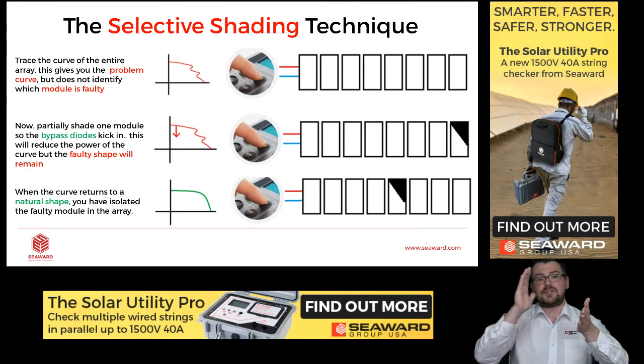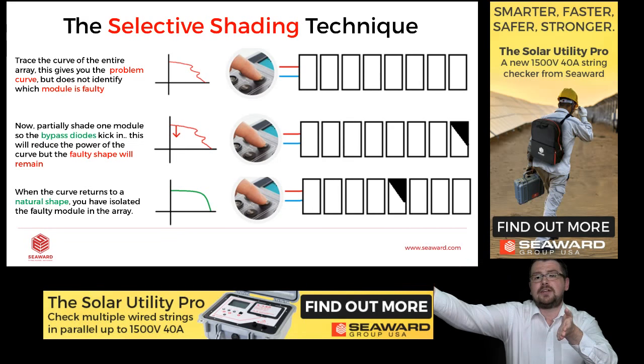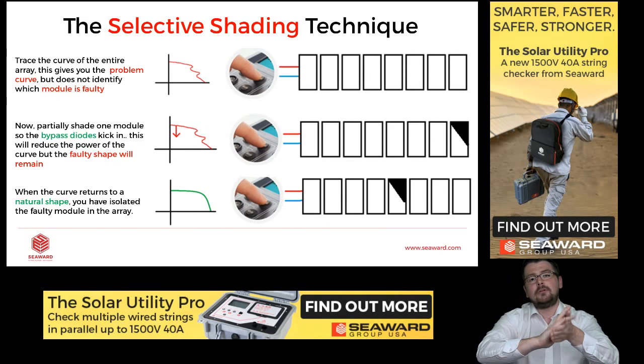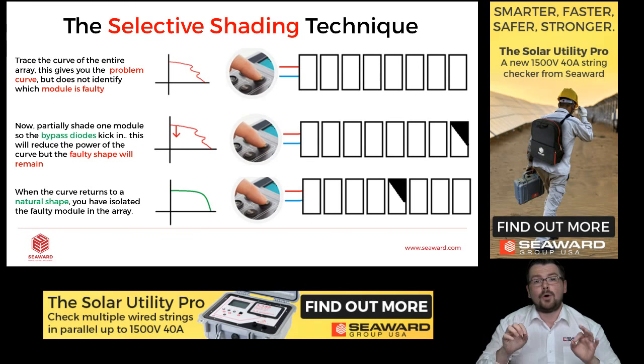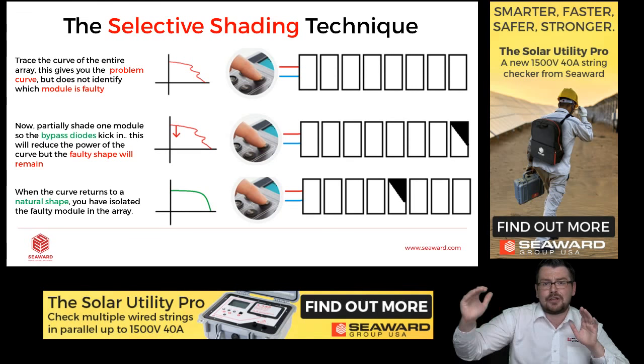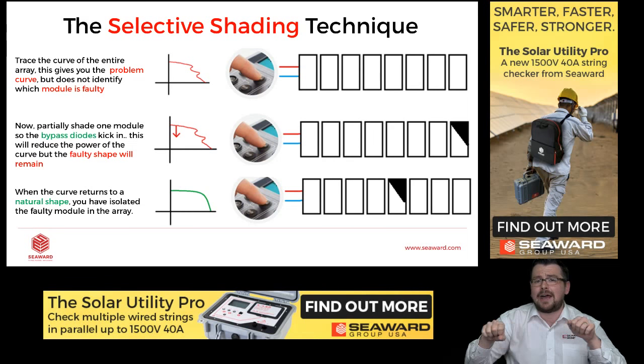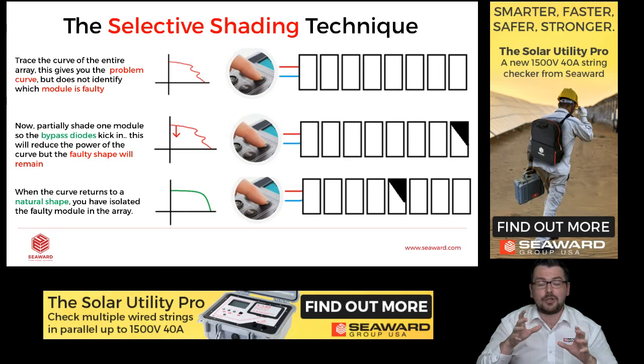So what we need to do is shade, curve, shade, curve, shade, curve, until we shade a panel and our IV curve turns to its natural bent knee shape. What that means is we've identified the faulty panel by this selective shading method. So this is a very powerful tool for fault finding, particularly on 1500 volt strings where you have 30, 40 panels in a string. You don't want to have to disconnect each of those. So by perfecting this method, you can quickly and easily find out where your problem module is.